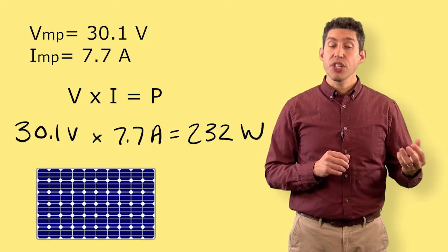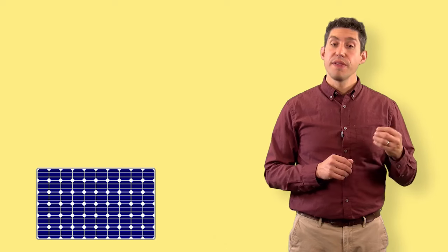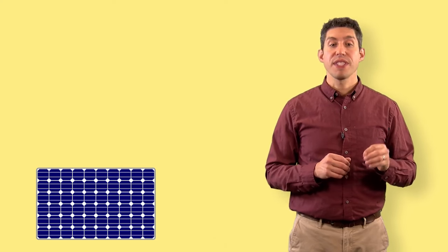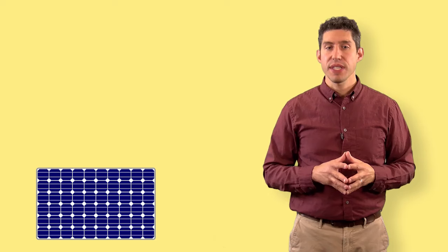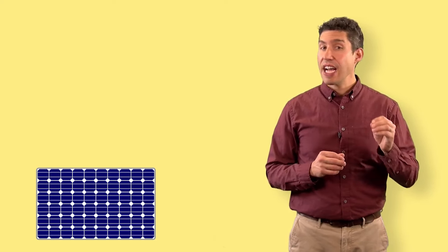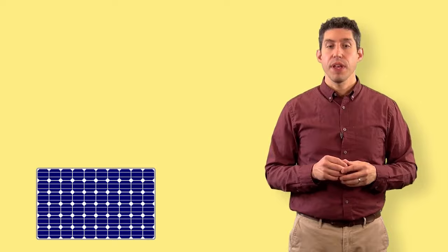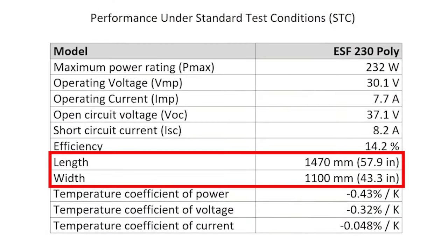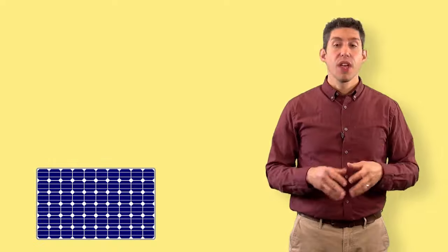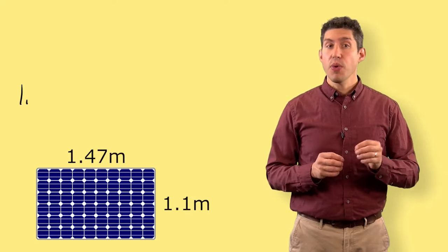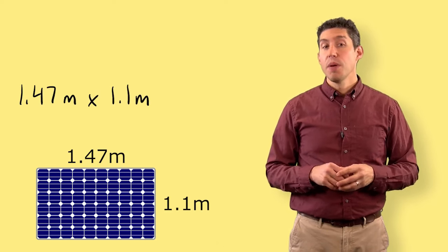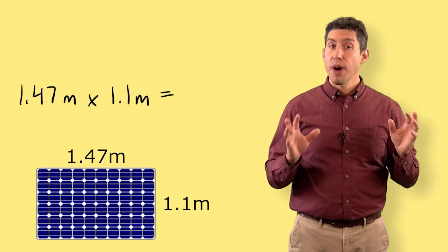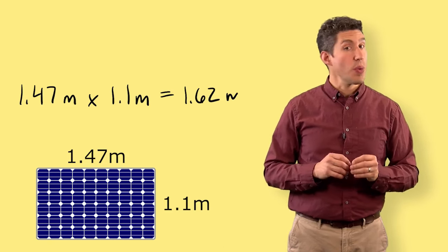The VMP and IMP are based off of standard test condition light levels. However, the panel is not one square meter in size, so we'll have to adjust for the size of the actual photovoltaic panel. The dimensions of the panel are listed on the specification sheet as well in units of length and width, usually inches and millimeters. For this particular panel, the length is 1.47 meters by 1.1 meters wide. Multiplying these two together gives an overall module area of 1.62 square meters.